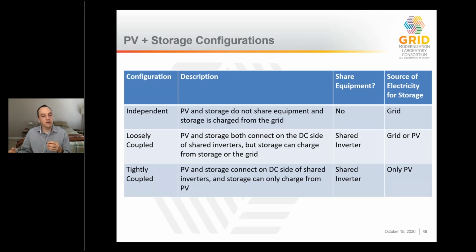One option is that we can connect PV and storage together on the DC side, which means we're sharing an inverter, but then still allow that storage to charge or discharge from the grid. That's what we call a loosely coupled configuration, sharing some inverter, but the storage is charging from the grid if it needs to.